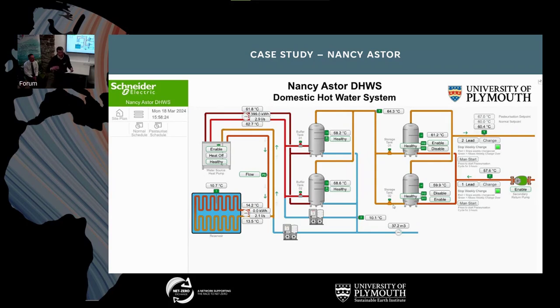So we're getting about 55 degrees, we need to store it at 60, 65. So it's boosted up at the final stage using direct electrical input. That also allows us to carry out the weekly anti-Legionella function, where we have to raise the temperature for a set period of time to ensure the water hygiene is retained.